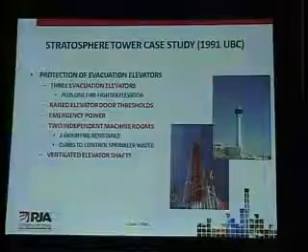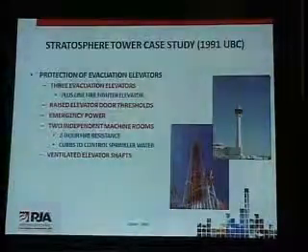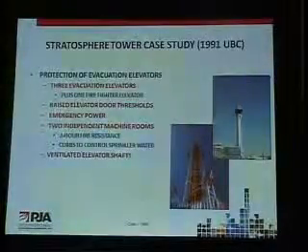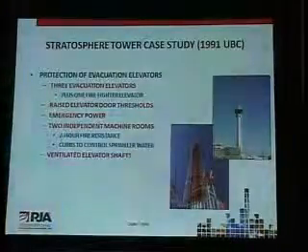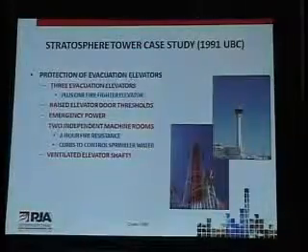One thing that they did do to increase the reliability of the systems is implement 2 independent machine rooms to make sure that if there was an incident that affected one machine room, the other machine room would still be protected, and that at least we're not compromising all of the elevator evacuation, just at worst 2/3 of it.